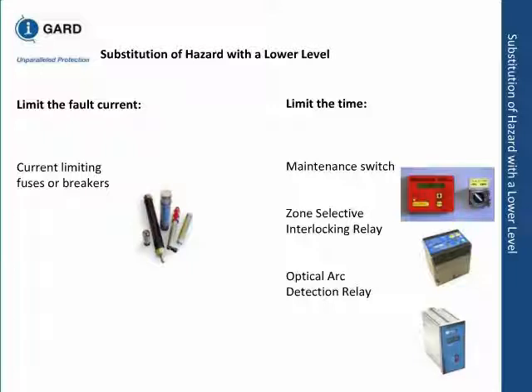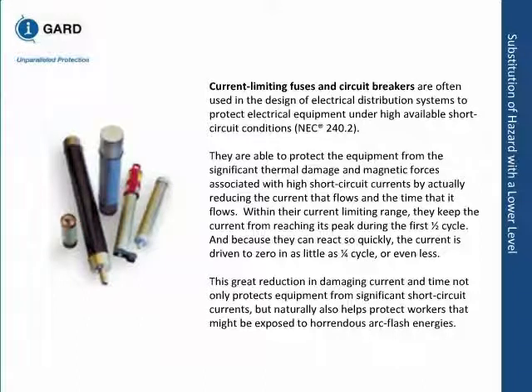Current limiting fuses. All of you are probably familiar with the NEC, the National Electrical Code. In 240.2, they will tell you what is required for a current limiting fuse. You can use it when there are very high fault current conditions. They protect the equipment from significant thermal damage. Now keep that in mind when you're using a current limiting fuse. Any breaker downstream may or may not be protected. That's a pretty common misconception, that everything downstream is protected. For a downstream device to be protected, you have to have a passive device, something that will allow the current limiting fuse to blow. Otherwise, you'll have transferred the problem to the downstream equipment.